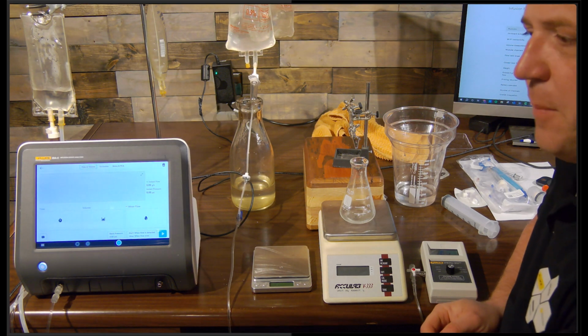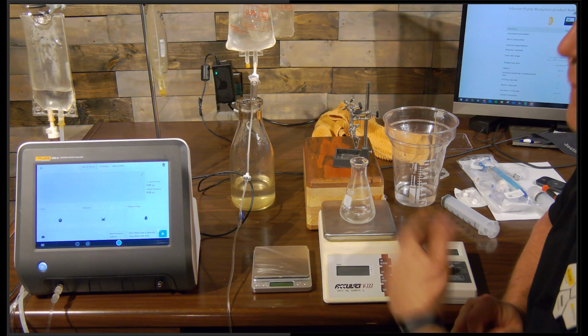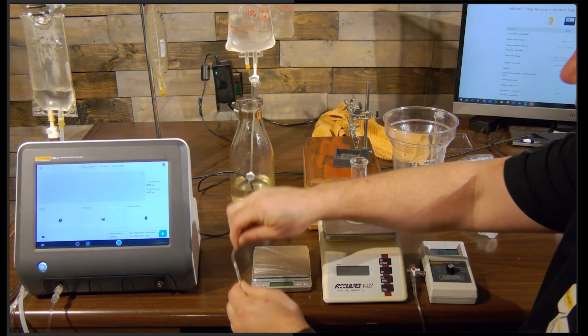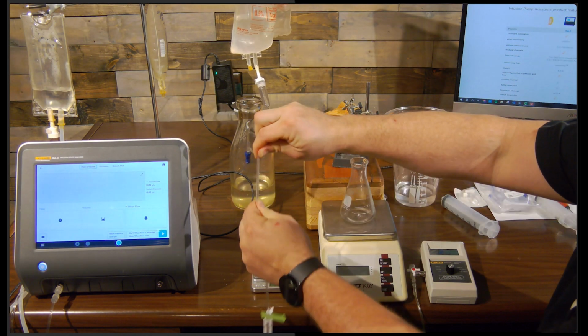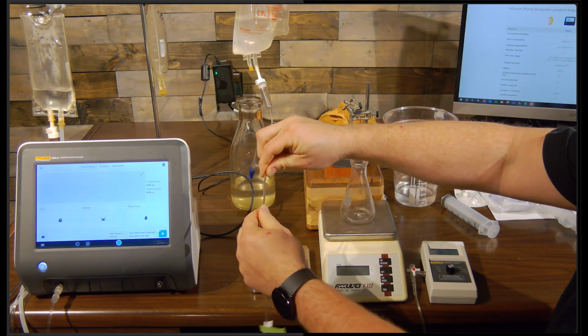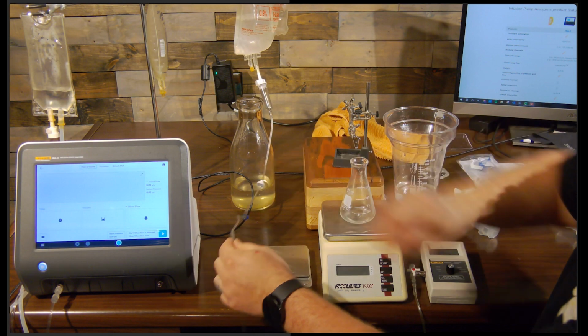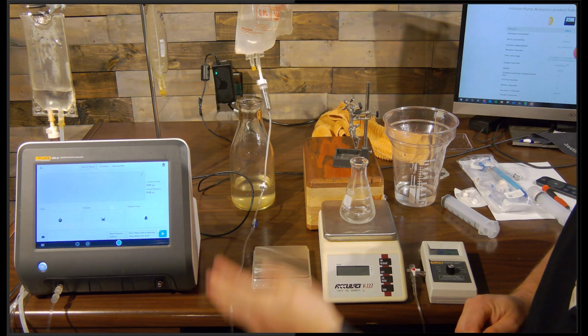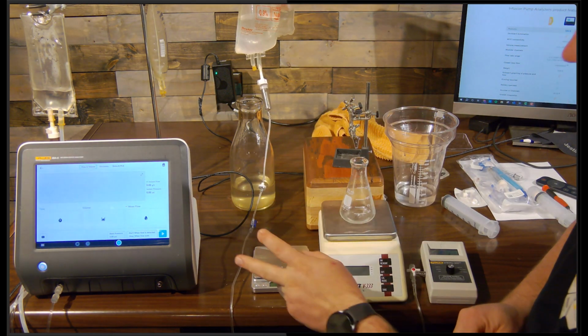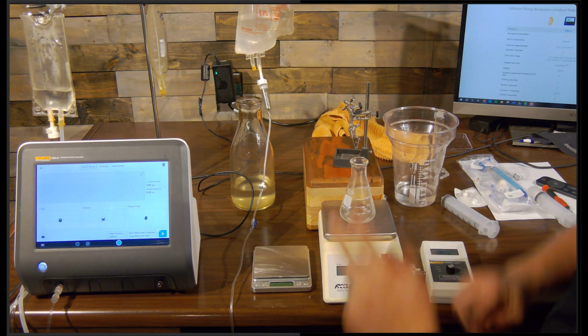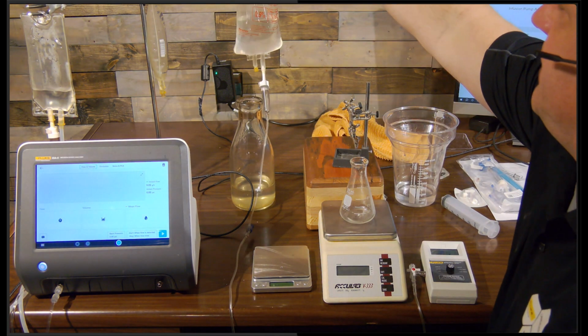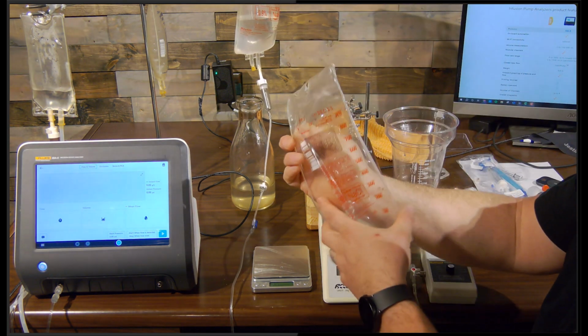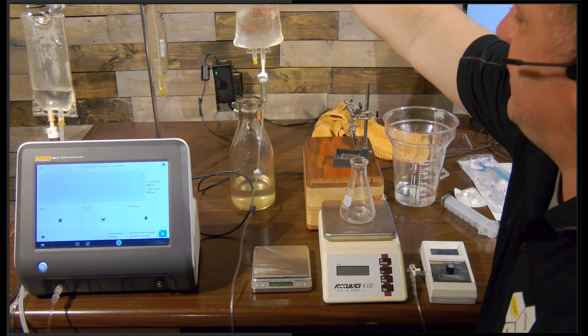When it comes to your pressure tests, you have to use a different set of tubing, because if you pressurize your calibrated tubing, it's going to stretch it out and change the memory on it, and it might change that rate. So you need to use 2 different sets of tubing. So if you do that, now you need to have a second bag up here. And let's talk about these bags, because you'll notice this bag has a big hole in it.